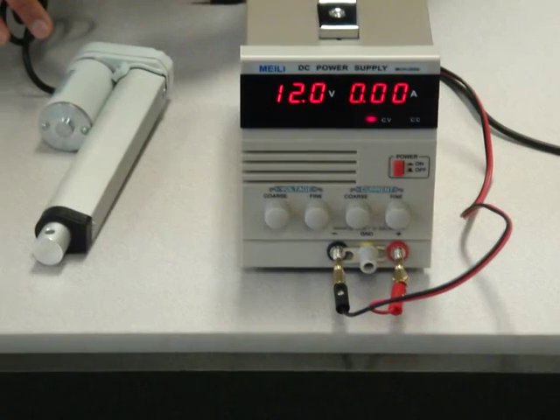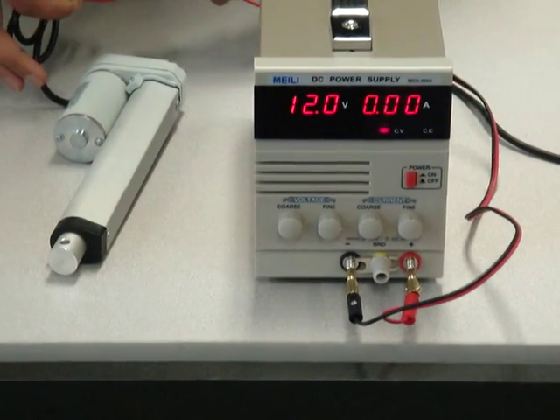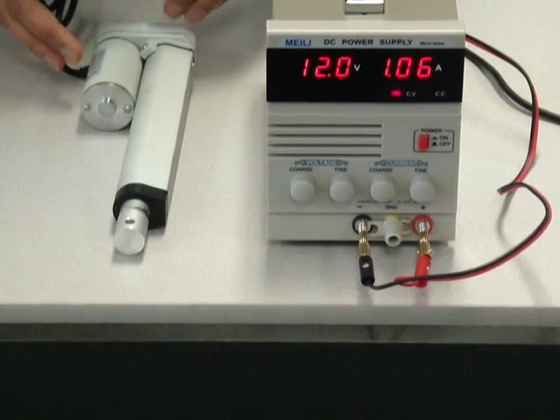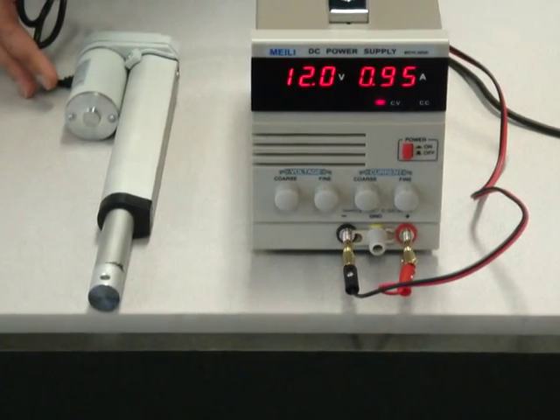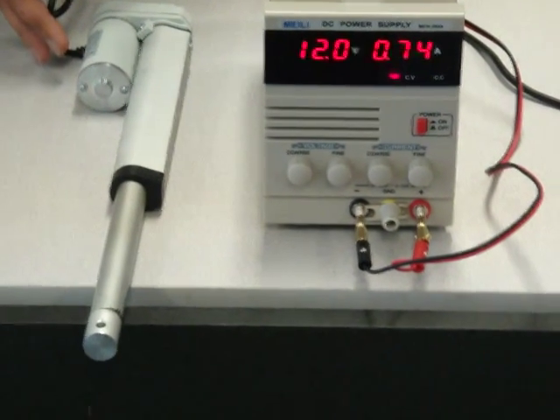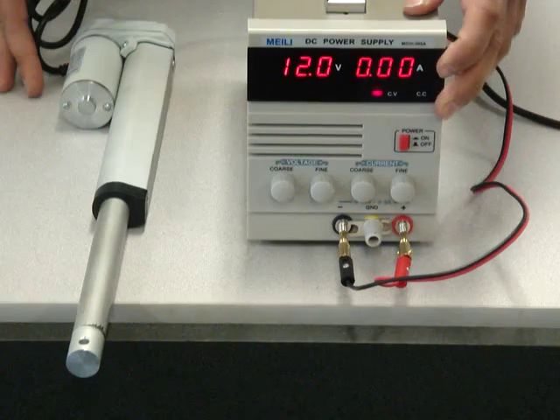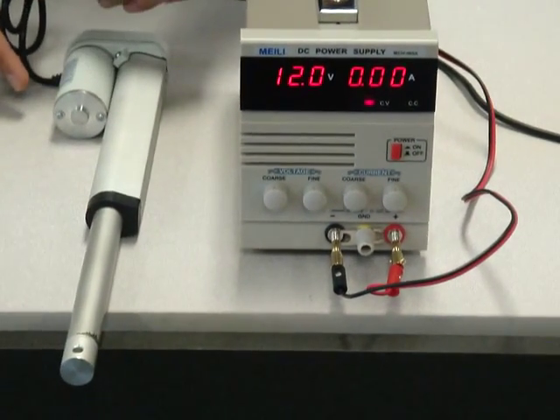I'm going to add the power to the actuator and as it extends you will see the amperage increase. As you can see once it fully extends the amperage goes down, the amperage draw goes to zero and the power has been cut off.